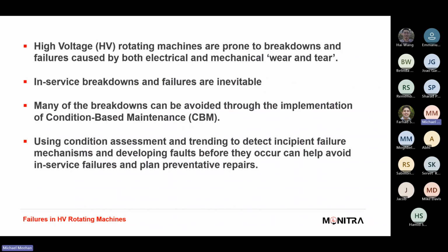So in summary, we've identified that high voltage machines are prone to breakdowns, and failures occur from both electrical and mechanical wear and tear. In-service breakdown and failure, we say it's inevitable, but it is if you don't do any maintenance and you just expect the machine to run. Typically, the bigger the machine, the larger the stator, the longer the stator core, the more arduous the operation, the more condition monitoring and the more attention to maintenance practice is going to be needed. By using condition assessments and trending to detect incipient failure mechanisms and developing faults before they occur, you can help avoid these in-service failures, and you can plan for those preventative repairs.